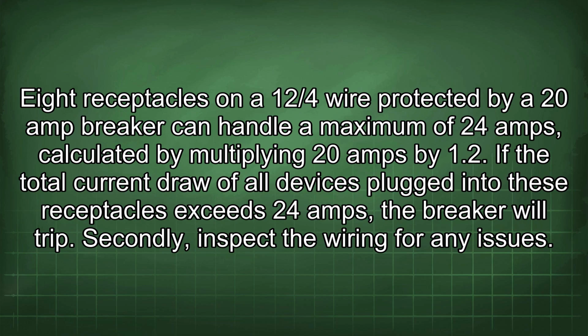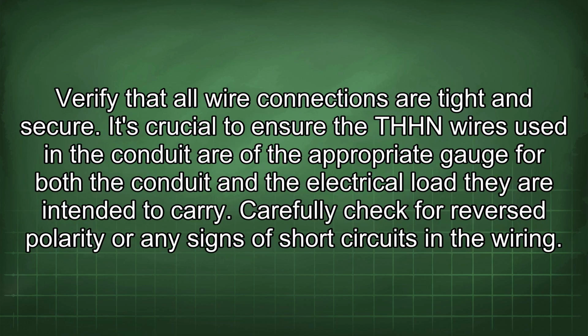Secondly, inspect the wiring for any issues. Verify that all wire connections are tight and secure. It's crucial to ensure the THHN wires used in the conduit are of the appropriate gauge for both the conduit and the electrical load they are intended to carry. Carefully check for reverse polarity or any signs of short circuits in the wiring.